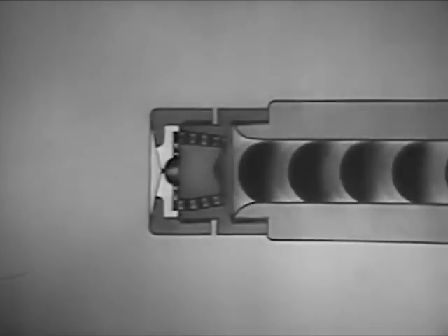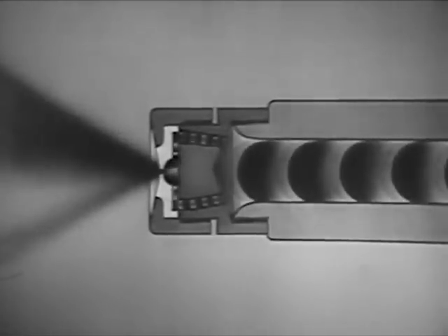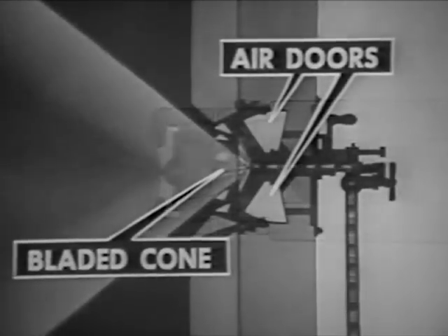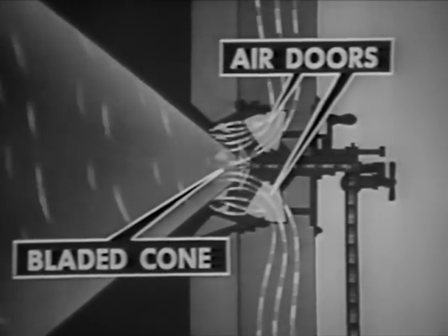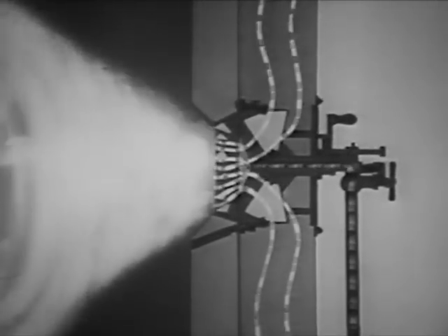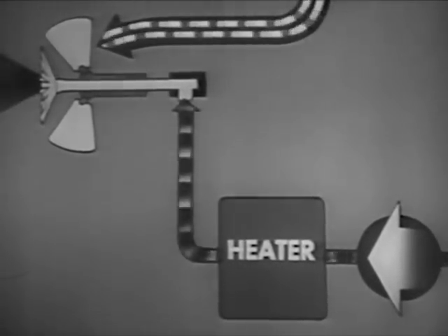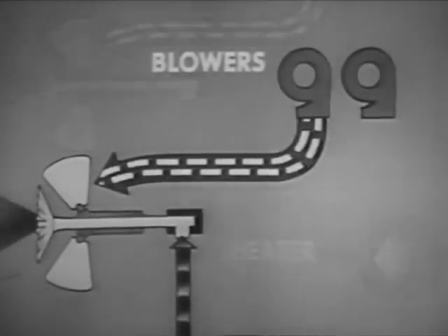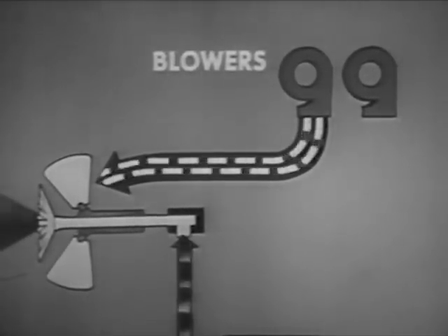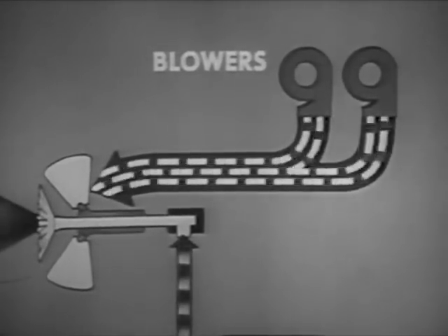In burners with mechanical atomizers of the pressure type, the sprayer plate atomizes the oil, heated and under pressure. The register gives the blast of air from the blower a rotating motion and mixes the air with the oil. You vary the pressure on the oil supply line to control the amount of oil entering the furnace. To control the amount of air entering the furnace, you vary the speed and number of the forced draft blowers.